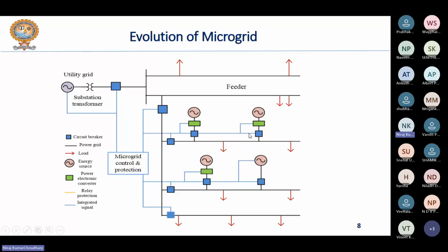So that information should be shared with the microgrid central control and protection unit, such that the load demand of that particular feeder can be fulfilled by the nearby DG present in the system. So this was all about the evolution of the microgrid system.